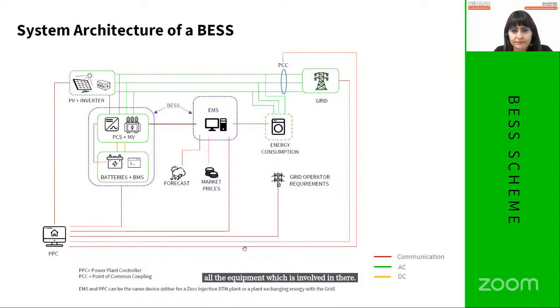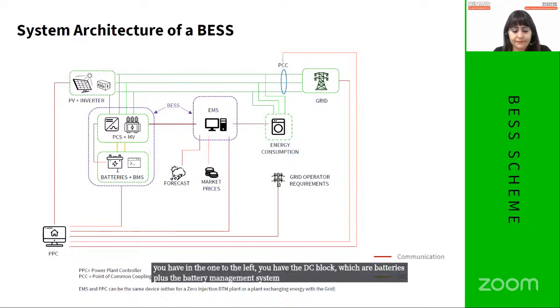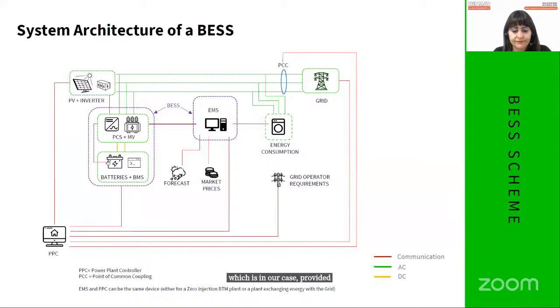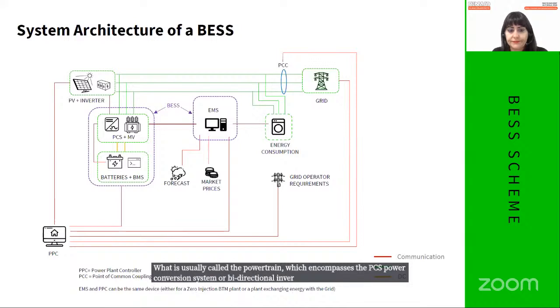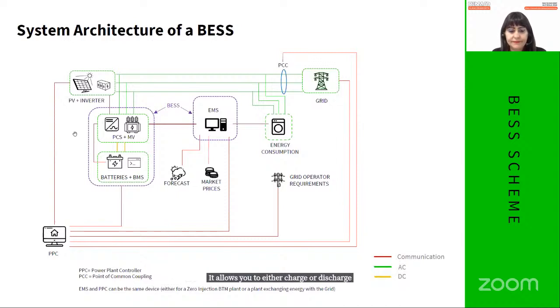What equipment is involved? We have these small purple boxes shown here. To the left, you have the DC block, which is the batteries plus the battery management system, provided in our case by the battery manufacturer. Then you have what's usually called the powertrain, which encompasses the PCS - power conversion system, or bidirectional inverter. As Juan Carlos mentioned, it allows you to either charge or discharge the batteries, plus the medium voltage elements, which may or may not be needed depending on whether you're connecting to a low voltage grid or a medium voltage grid.